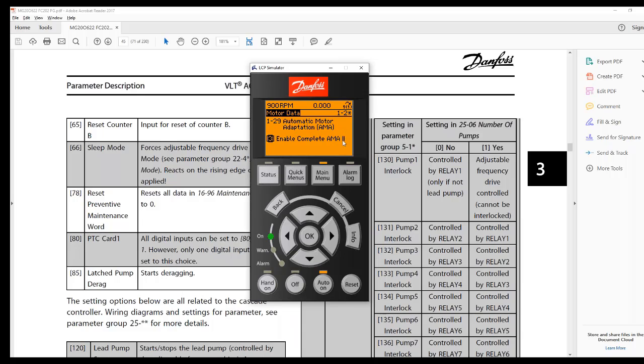AMA2 is a different AMA, mostly with permanent magnet motors in mind. And I think these aren't for standard asynchronous motors, which I've tried the two. I think on a synchronous motor, it will go very fast and just everything's fine, but the numbers don't change. So what I was told is the AMA2s are for permanent magnet motor tuning, but the AMA1s do tune permanent magnet motors also. This one's just a faster function, I think more DC reactance and stuff. But that's the difference.